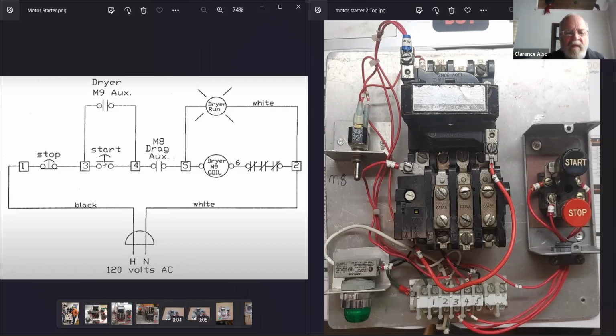So if you hit the start button, and if this is tripped out, you're going to have 120 volts here. Auxiliary is on, so it's going to go across here. When you push the button, the coil's not going to come in because it doesn't have connection to neutral - you don't have the 0. In fact, if you do push the button down, this here is going to say 120 volts. If this is broken, Isaac, what is number 6 going to say?